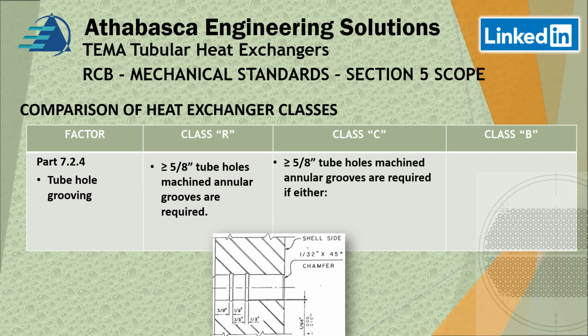For Class C, the same rules apply, but there are some exceptions. So it's required only if the design pressure is 300 psi G, and the design temperature is greater than 300 Fahrenheit. And for Class B, just follow the rules of Class R.